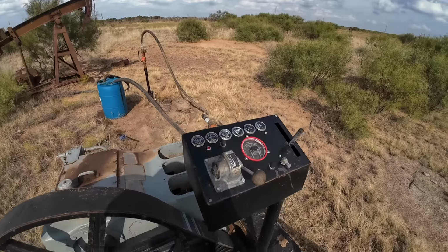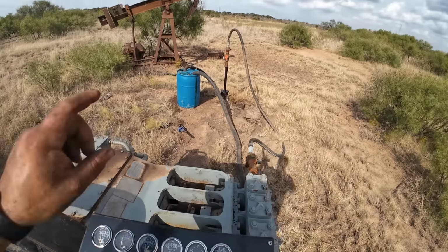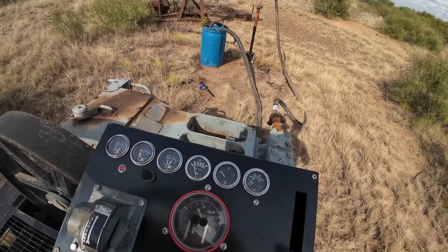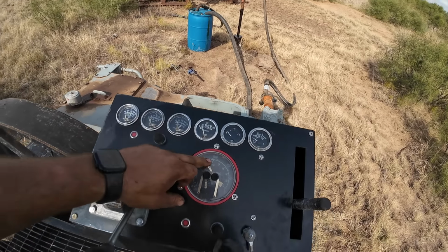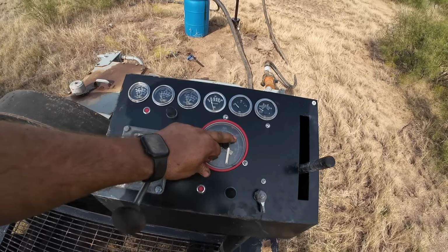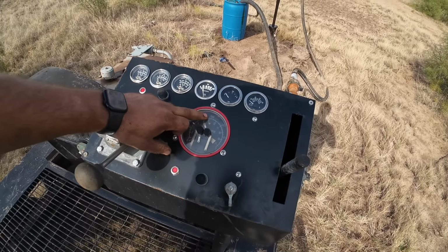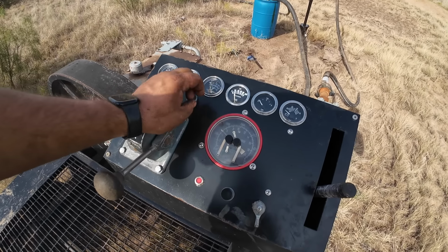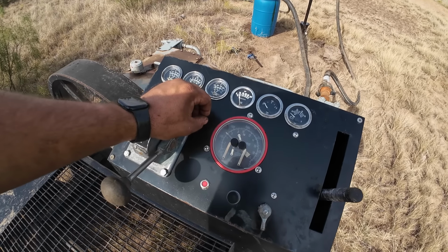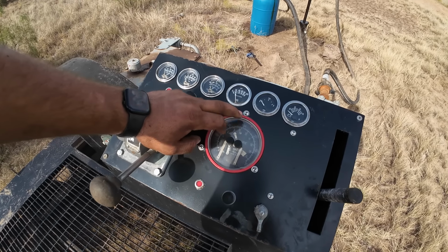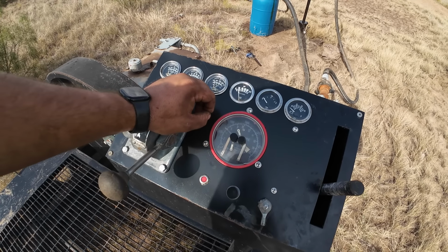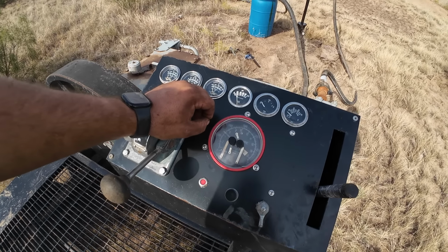Alright, so I did exactly what I didn't want to do - I ran it dry and sucked air up in the pump. It was actually getting better. If you remember, initially we got up to close to 2,000, and that pump the whole time got up to about 1,550. So we're going to keep doing this and see if we can make this get better.